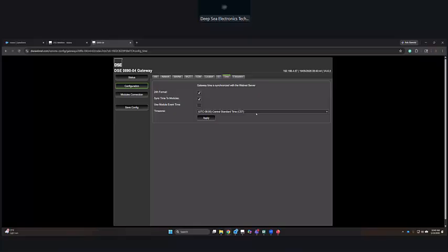And you can go in using Config Suite trying to fix that time, and it's always going to revert back to this. So if you don't want that to happen, just make sure that box is unchecked for sync time to modules, and then you can set your time in the DeepSea module genset controller without having to worry about it being changed by the 890.